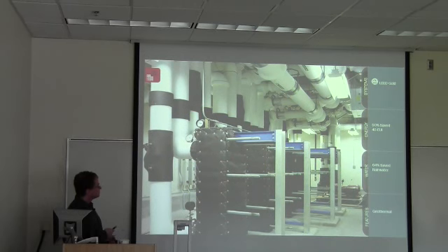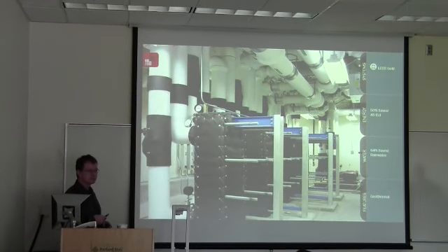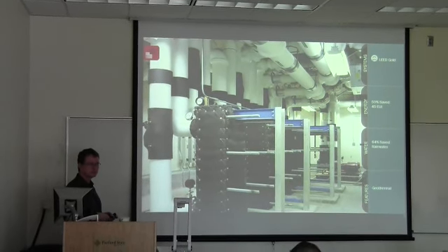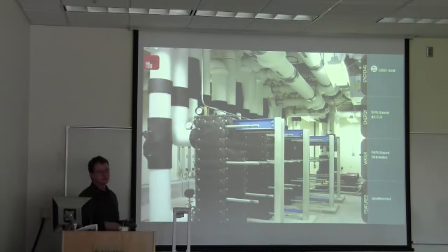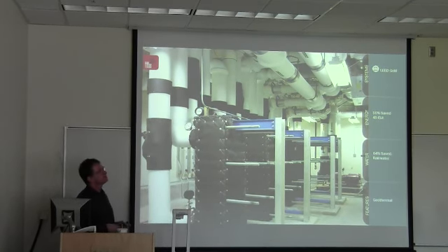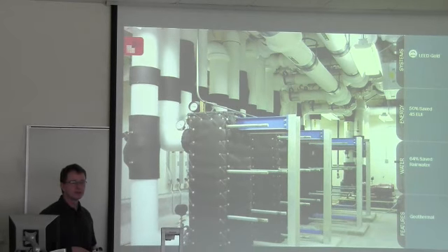These are the heat exchangers in this building that do the transfer of energy from the geothermal open loop system into the heating and cooling loops that are controlled from scroll compressor chillers within the building. There's a 200 and a 400 ton machine in the building. Most of the time this building runs on the 200 ton machine. It's well within the parameters. Only when the outside temperature is in the high 80s, I think the operator that I met with said, do they actually have to bring the larger chiller online. So the building's actually been operating quite nicely.